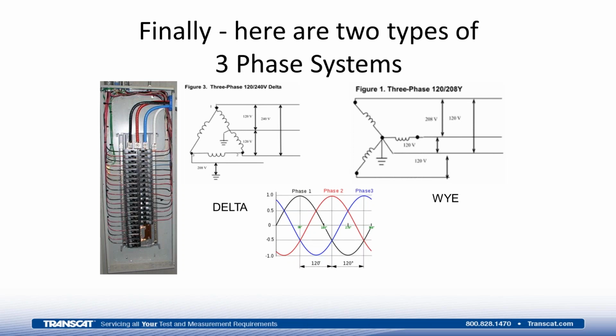And depending on whether you have a delta or a Y type feeding system to your facility, this gets to be more the semantics of the operation and not so much with the monitoring of the operation on how the wiring occurs in the facility. To monitor these loads, I would put three voltage leads, one on each phase. If I had a neutral present, I would provide the fourth lead. In the case here, this would be the white wire. I would connect up to that, and that allows me to measure all voltages feeding into this panel.